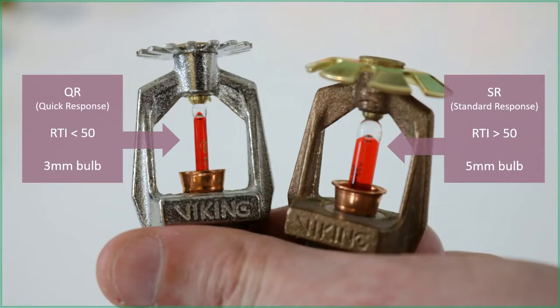I forget what the units are now, but it's linked with speed and the expansion of the liquid, but it's not as simple as saying it'll activate in 50 seconds, because that's not correct. But the RTI is a measure of the speed, and quick response has an RTI of less than 50. So it's a quick response head because it activates more quickly when it comes up to temperature.